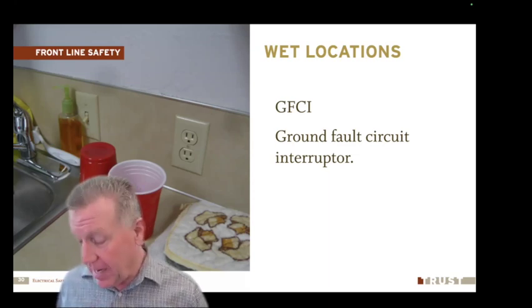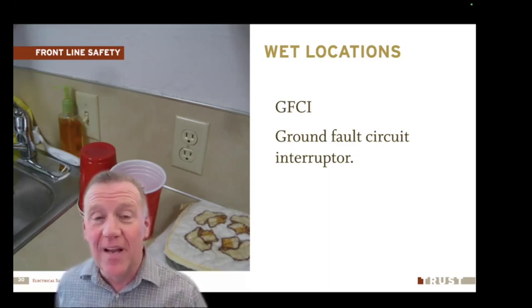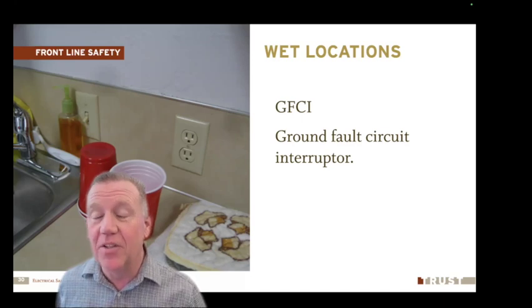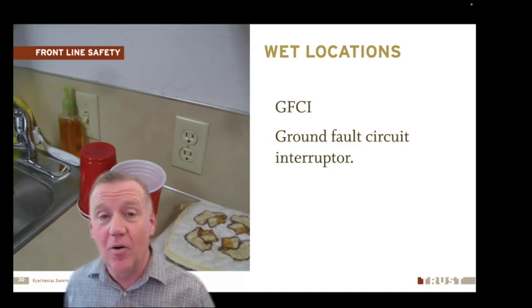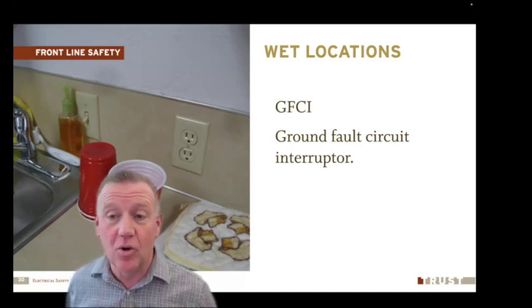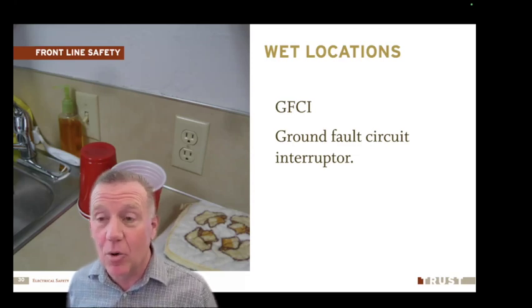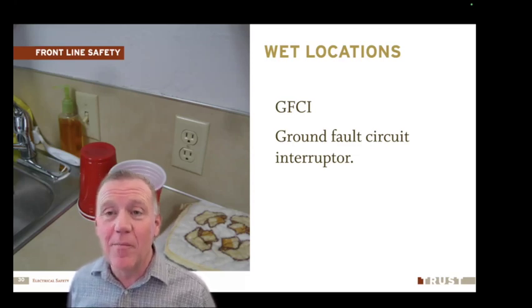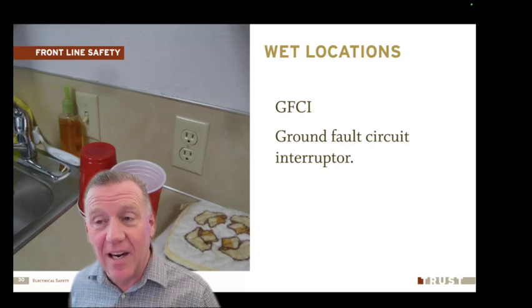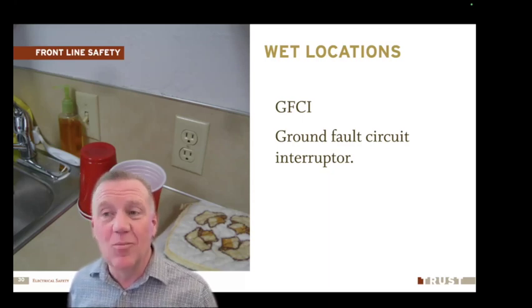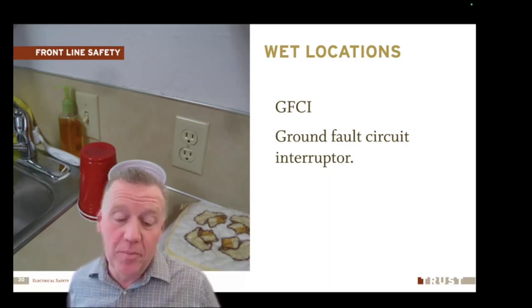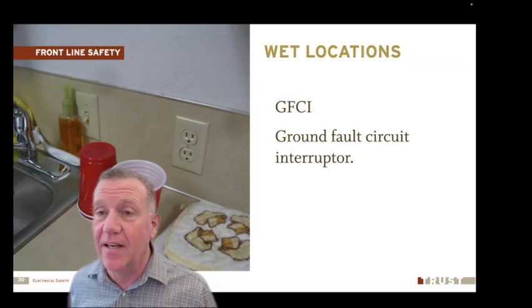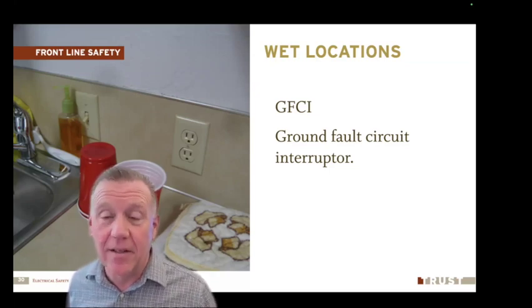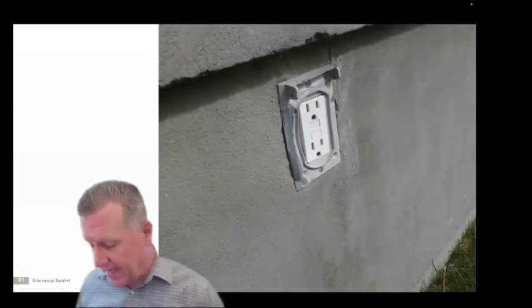If the thing's popping or tripping, that means there's a problem in your system somewhere. It could be wired wrong, or there could be a short, or there could be a problem with the appliance we're plugging in. Just don't get mad at the GFCI. Realize that's a problem somewhere in the system. It could be the actual outlet if it's failed, but in many cases it's something else, and that's telling us there's a problem. So don't ignore that.